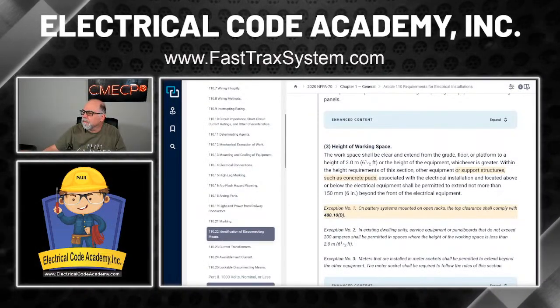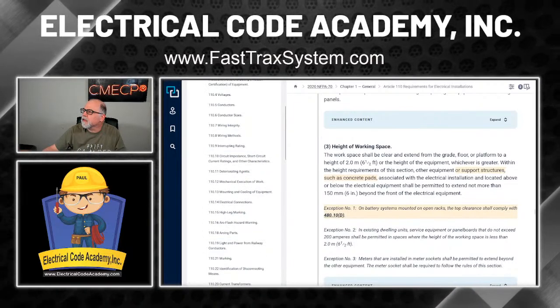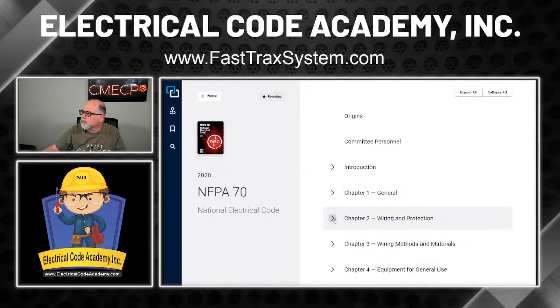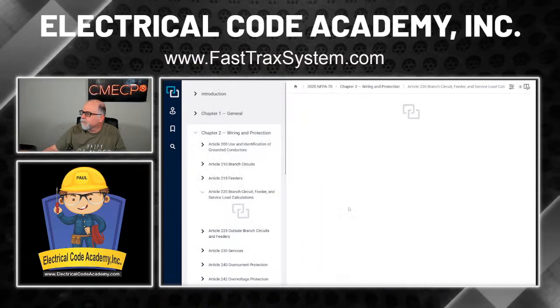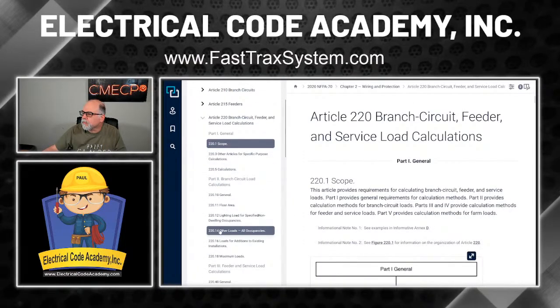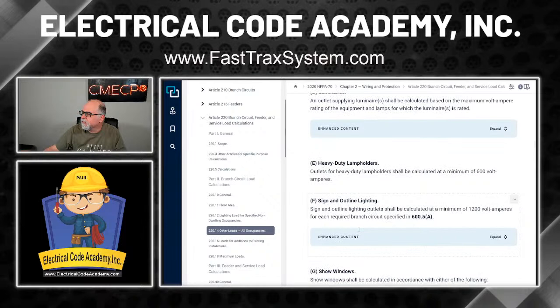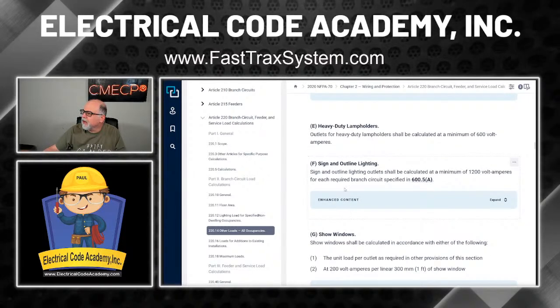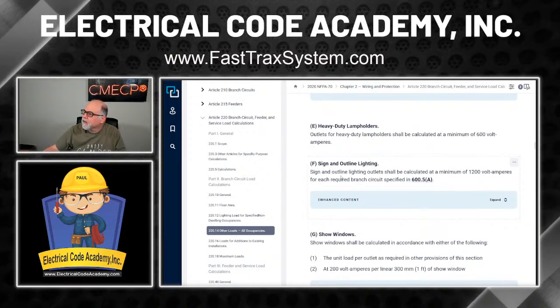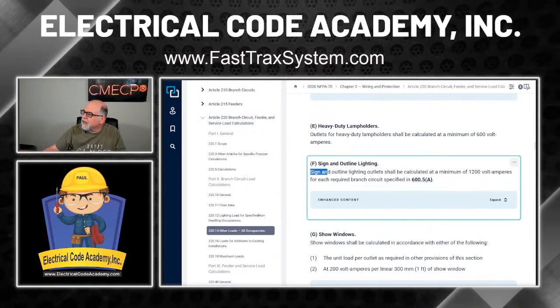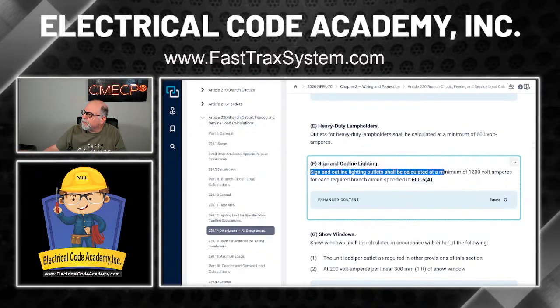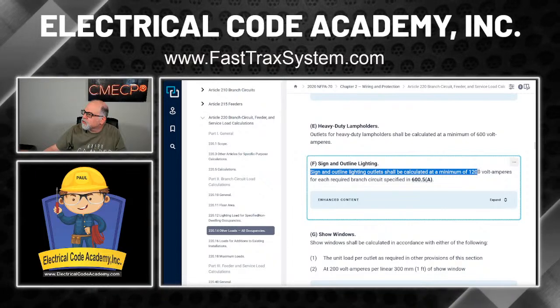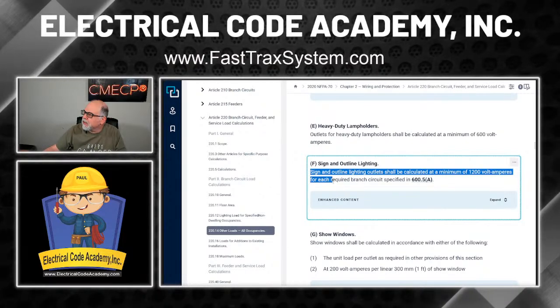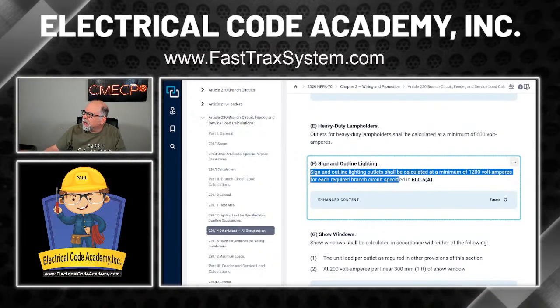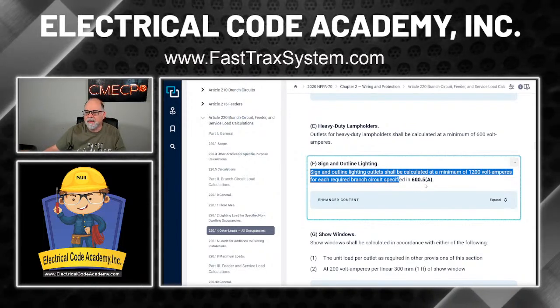And let's see here. Go back to the code here. Let's go to 220.14. Right here, and we've got to go to F. All right, here's F right here, okay? Now it says, sign and outline lighting outlets shall be calculated at a minimum of 1200 volt-amperes for each branch circuit specified in 600.5(A), okay?